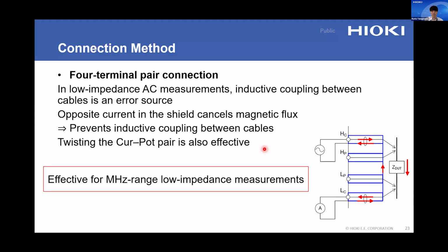Okay, finally, the last connection method is here, the four-terminal pair connection. For DC low resistance measurement, four-terminal connection is sufficient. However, for AC low impedance measurement, the situation is different. In low impedance measurement, the signal current becomes large, while the voltage sensing signal becomes small. As a result, the magnetic flux affects the measurement, causing inductive coupling between cables. To address this issue, the signal passing through the DUT is returned through the shield conductor. This cancels the magnetic flux and prevents inductive coupling between cables.